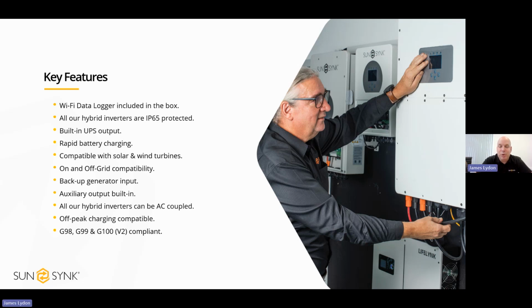Next one, we have an auxiliary output built in. So this works similar to your Eddies and your iBoost. So you can wire, there's an output on the inverter, which you can wire into an immersion. You can set the parameters on the inverter as to what power that immersion heater wants. So this is where we're a little bit different than some of the others on the market, where they will start diverting at, let's say, 200 watts or 250 watts. How our diverter works is you tell the inverter that the immersion wants 3 kilowatt.